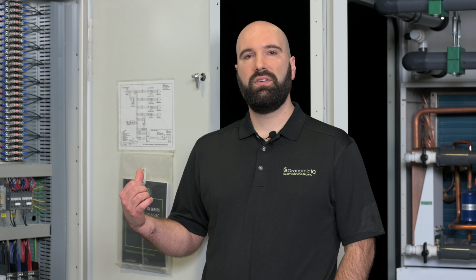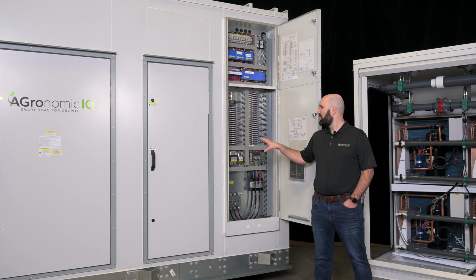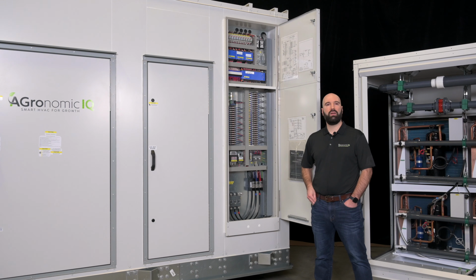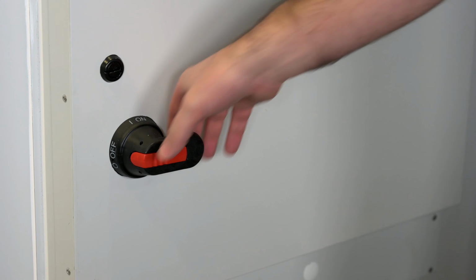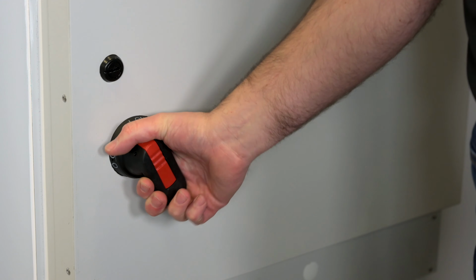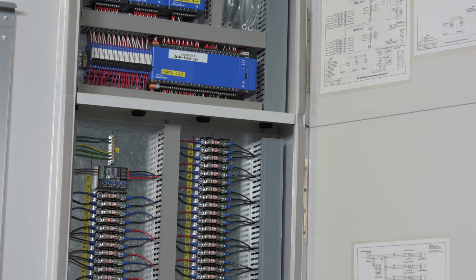So here we are on the electrical panel of this unit. Again, 55-ton unit. You can see a very clean layout in the high voltage panel. There's an integrated disconnect to ensure that it's very easy for your electrical contractor to complete their install work. That disconnect handle is a through the door style, ensuring again you're electrically safe before you open it.